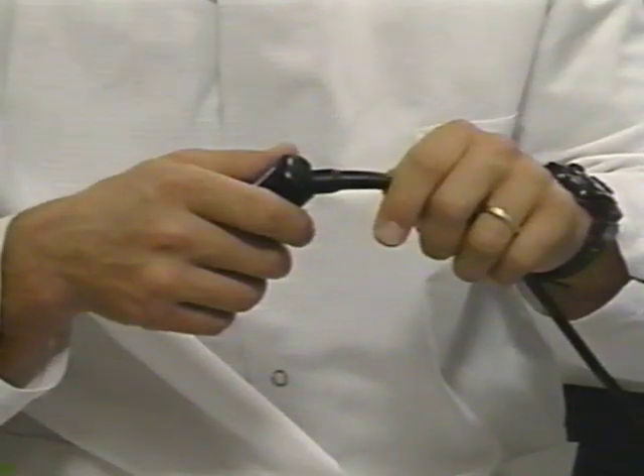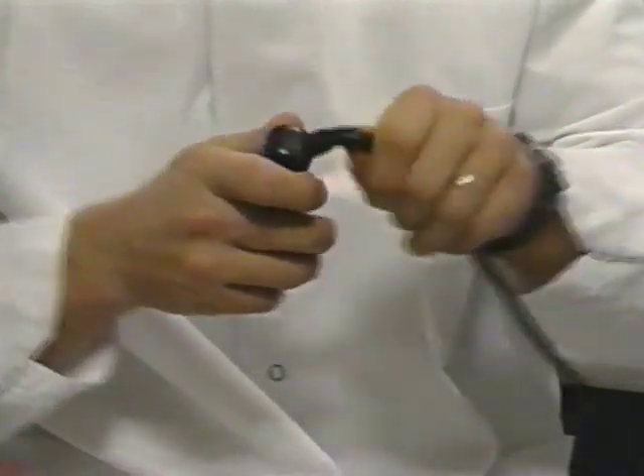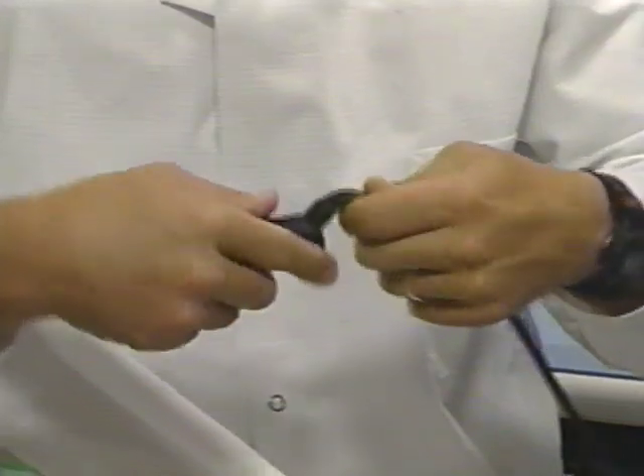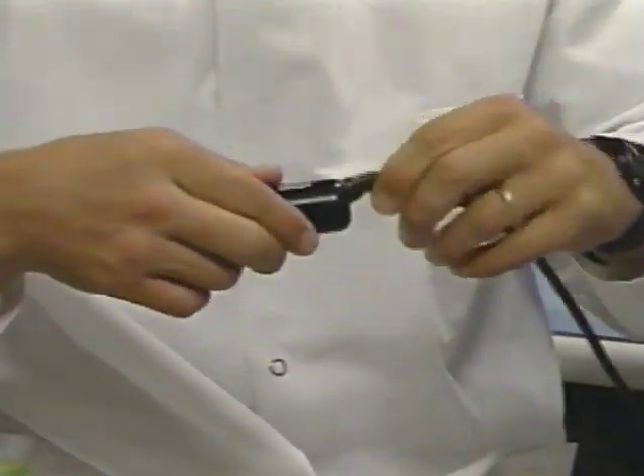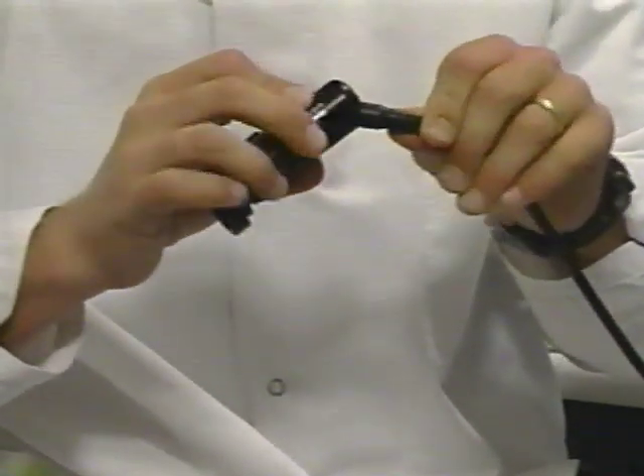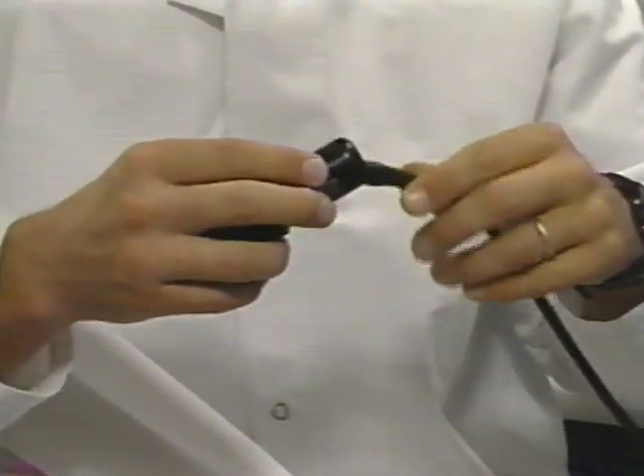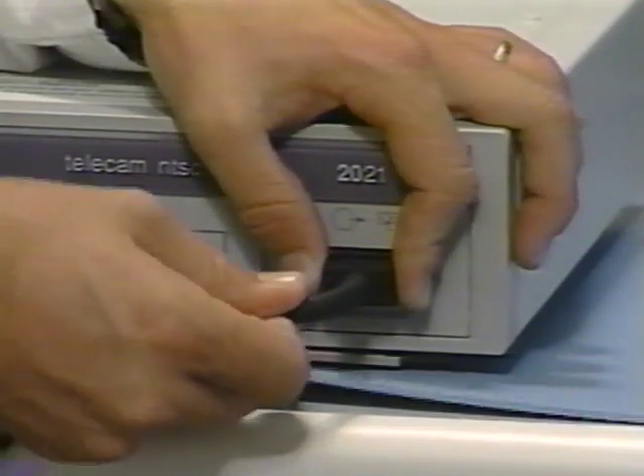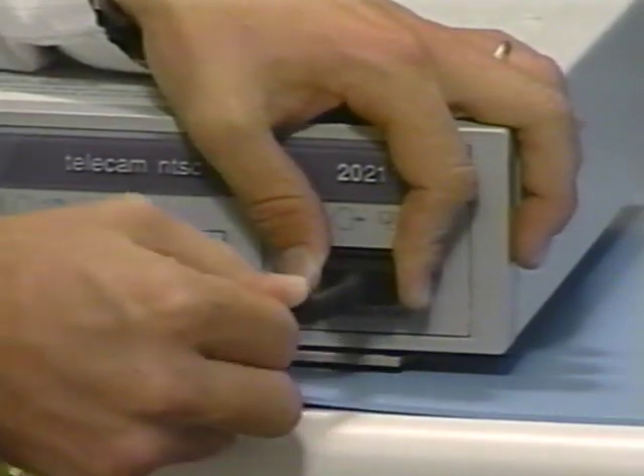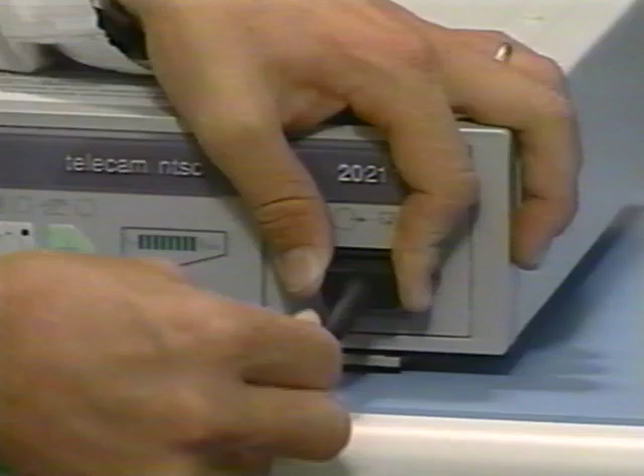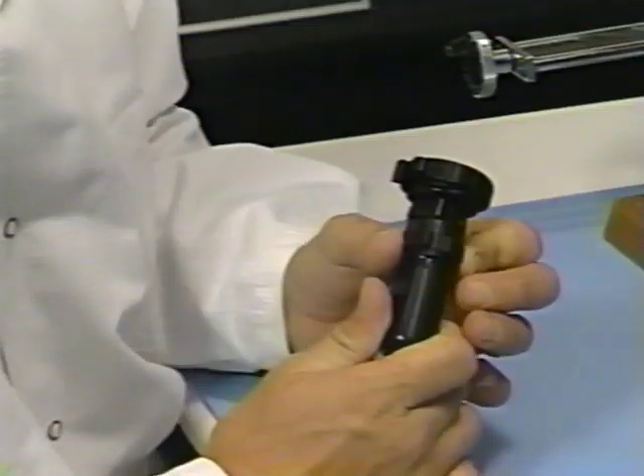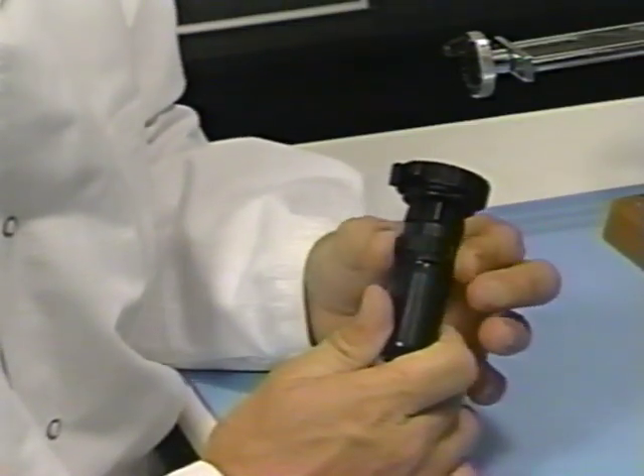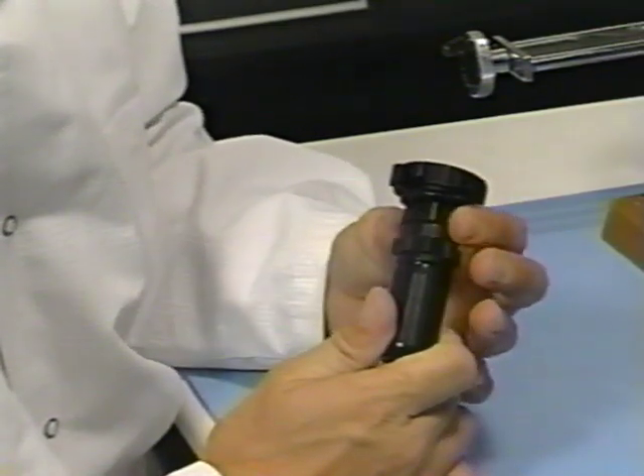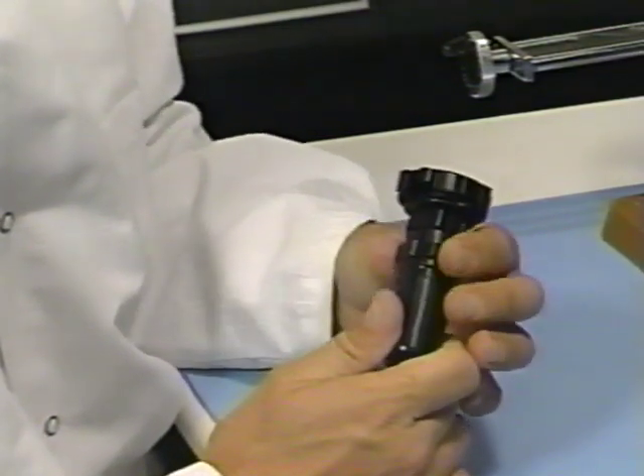If you suspect a damaged cable, manipulate the cable strain relief at the head and connector ends to look for noise or loss of picture. If the problem area is close to the head, it is likely to be a damaged cable. If at the connector end of the cable, there may be a problem in the CCU cable receptacle. Operate the focus and zoom mechanisms through the whole range to check for distortion or mechanical problems.